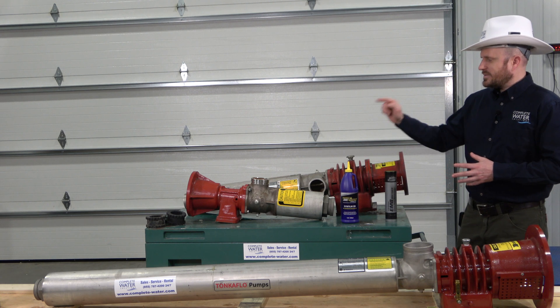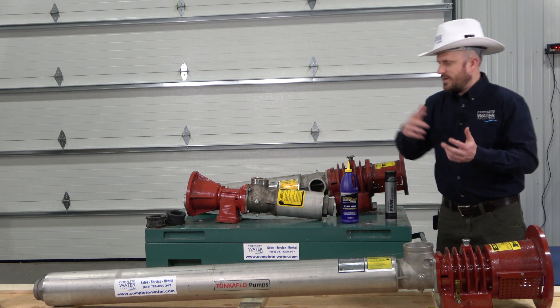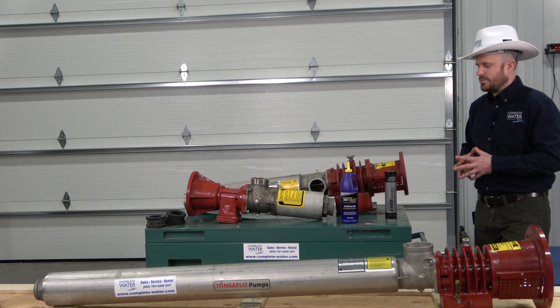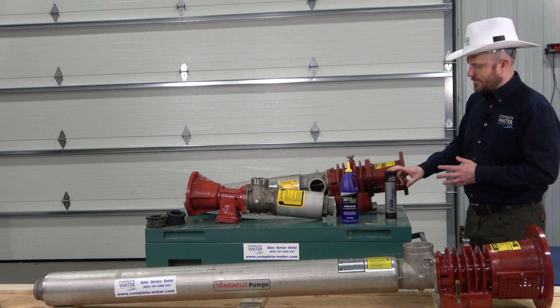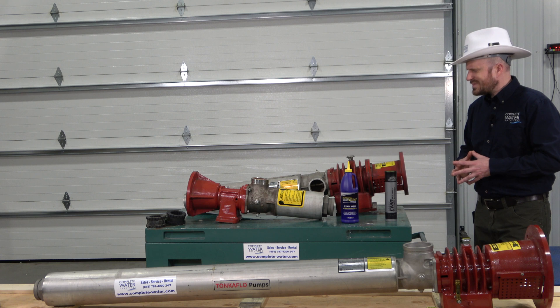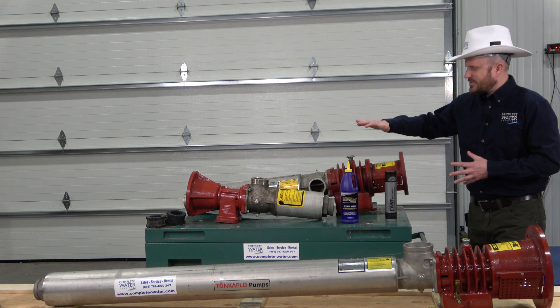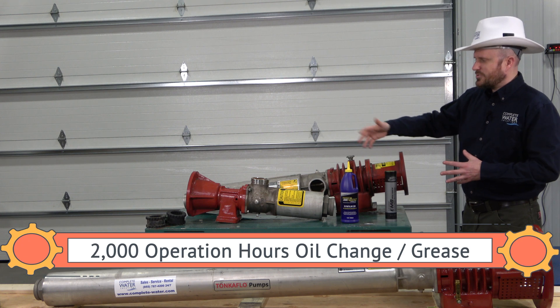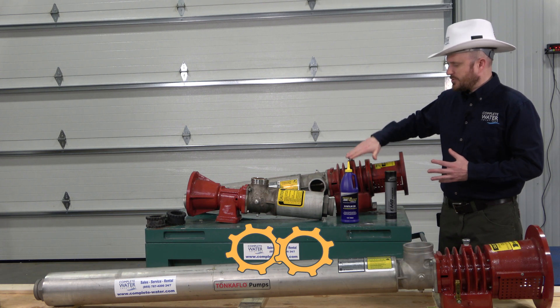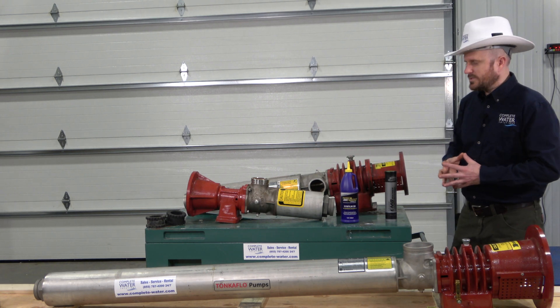As far as the gearbox goes on these, where they have Zerk fittings, they may take a grease. Within the Tonkaflo pump manual, it will tell you to use an EMB or EMD series bearing grease. As they say, every 2000 hours of operation you should be greasing or changing the oil out in your pump — minimal two times a year on this bearing frame assembly, and on that one, minimal one time a year.